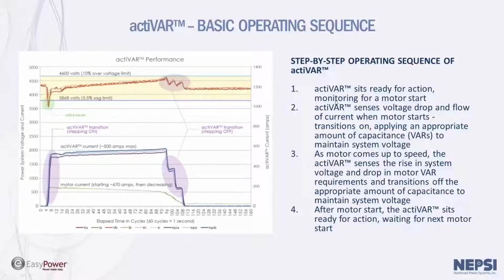The other interesting thing about the actiVAR is that after the actiVAR operates and starts that first motor, it will sit ready for operation for the second motor. And there is no necessary 5-minute waiting period as with a conventionally switched bank. When you use a conventionally switched bank with breakers and switches, once you open the capacitor bank breaker or the capacitor bank switches, you must wait 5 minutes for a discharge period before you can re-energize. In a thyristor controlled capacitor bank, there are diodes that are anti-parallel to the SCRs. The diodes keep the capacitor bank at a negative peak, and as such they can be turned on without that necessary 5-minute delay that you would see with a conventionally switched bank.